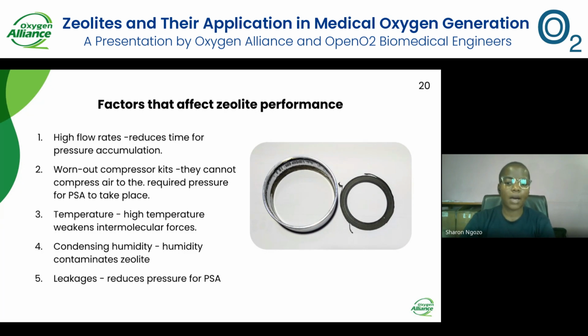Secondly, we'll talk about the compressor performance. Here we'll talk about the worn out compressor kits. As you all know, the compressor is one of the components that's really vital in the production of oxygen.